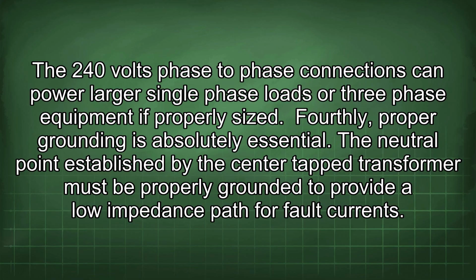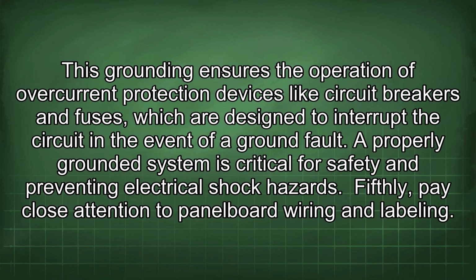Fourthly, proper grounding is absolutely essential. The neutral point established by the center tap transformer must be properly grounded to provide a low impedance path for fault currents. This grounding ensures the operation of overcurrent protection devices like circuit breakers and fuses, which are designed to interrupt the circuit in the event of a ground fault. A properly grounded system is critical for safety and preventing electrical shock hazards.